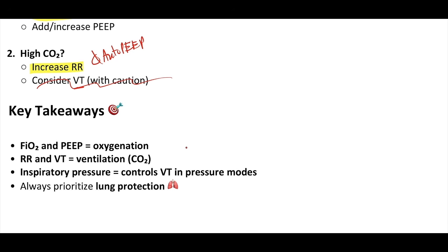Key takeaways to wrap it up: FiO2 and PEEP are what drive oxygenation. Respiratory rate and tidal volume drive ventilation. Inspiratory pressure controls the tidal volume in pressure control modes, and always prioritize lung protection.